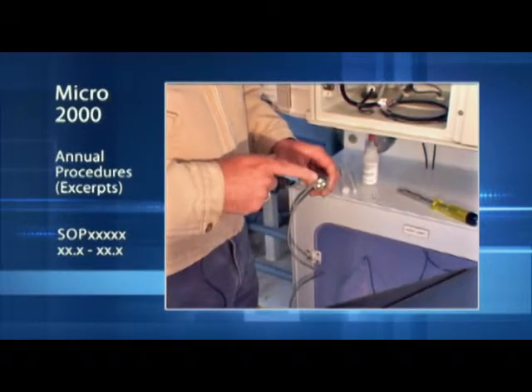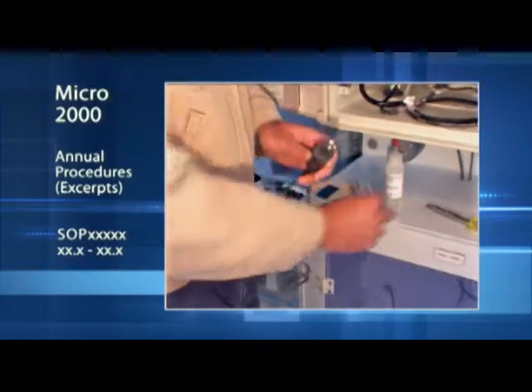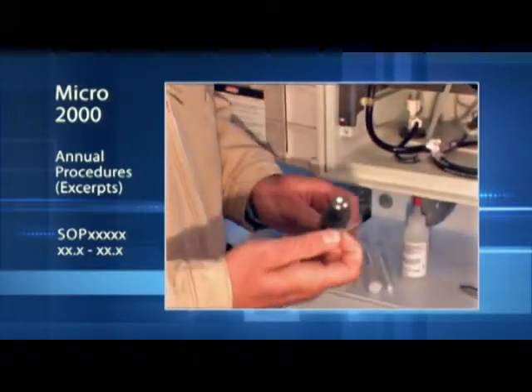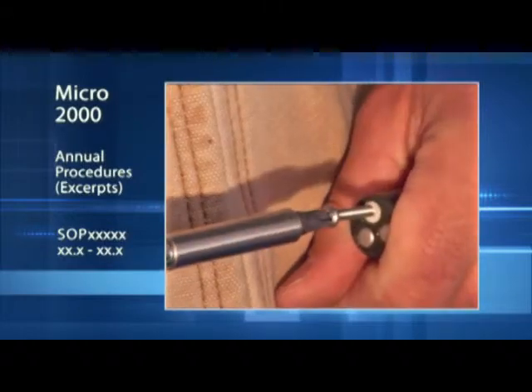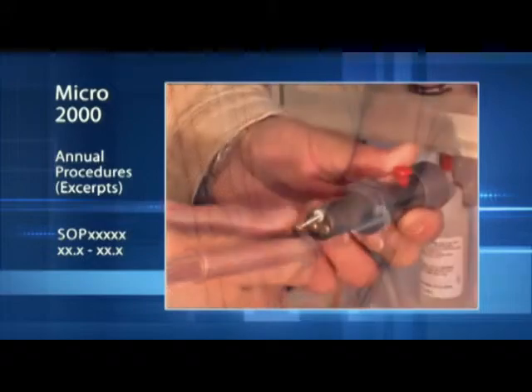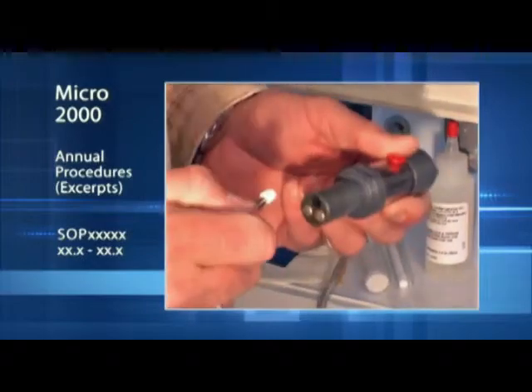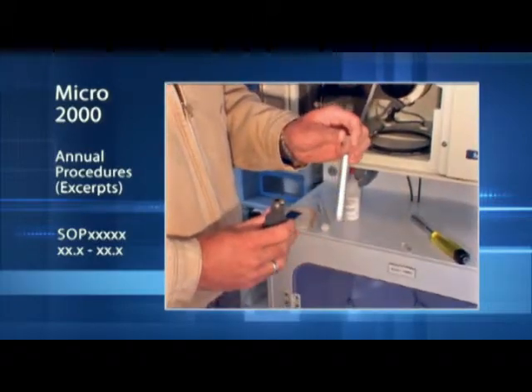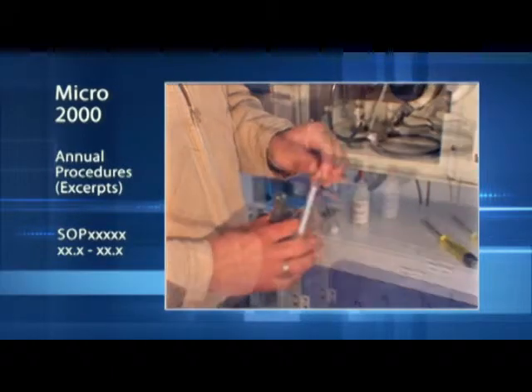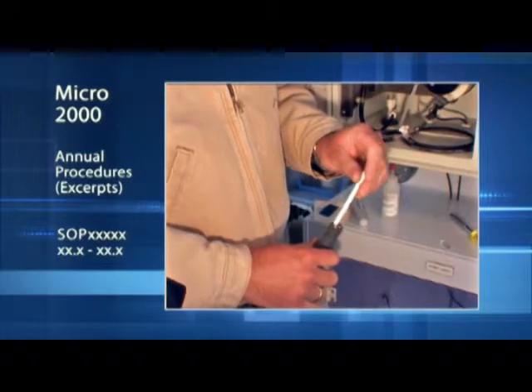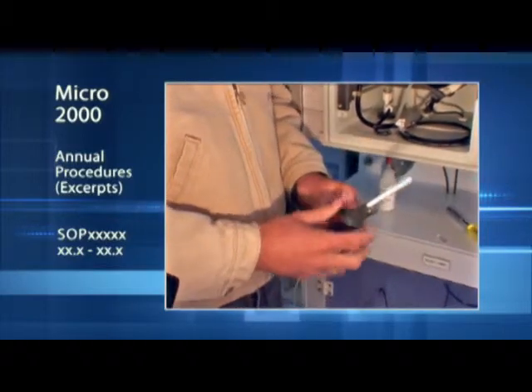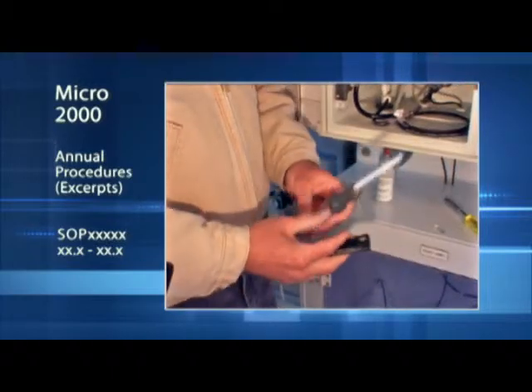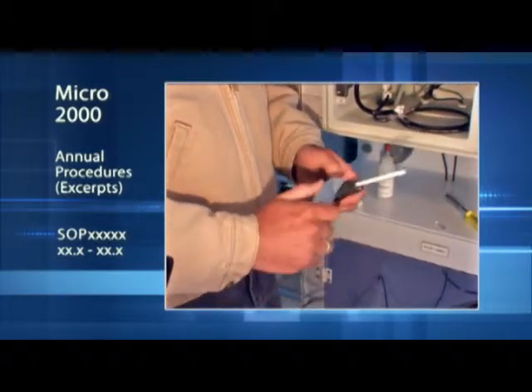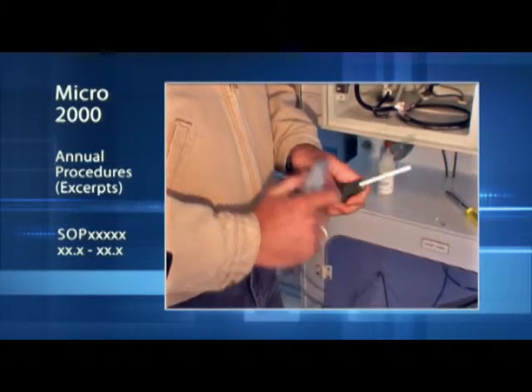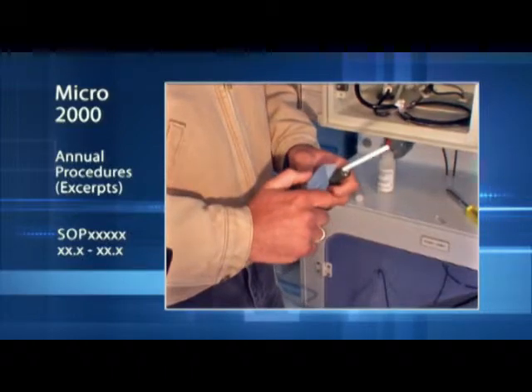The next step is to replace the white porous tip in the end. Using a simple screw, screw it into the white element, grab the screw and wiggle the porous element out. Grab the replacement elements from the maintenance kit, remove it from the tube. Place the element inside the probe until it bottoms itself out. Then using a sharp knife or razor blade, you can trim the element flush with the end of the probe, being very careful not to damage the titanium tips.